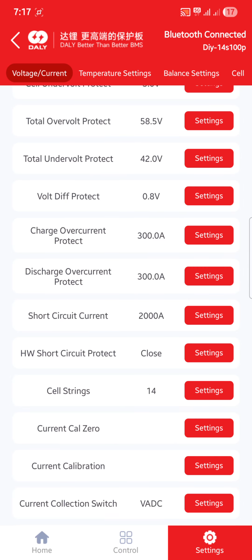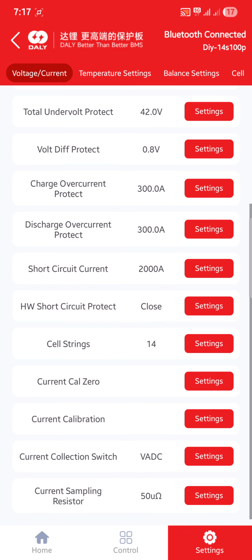Charge over current protect, 300 amps. Default is what the BMS can handle, rated 200 amps continuous. I think charge over current protect of 300 is not bad, but I'm still thinking I probably need to reduce that to 250 amps. Let's see, discharge, I did the same.